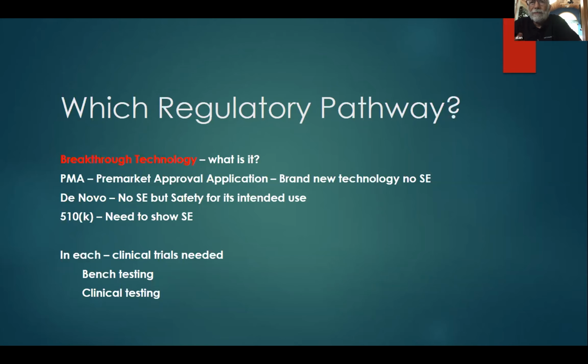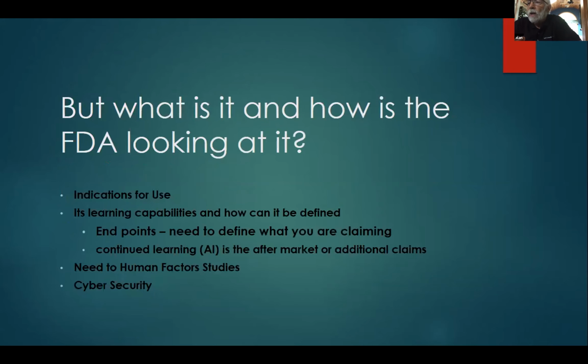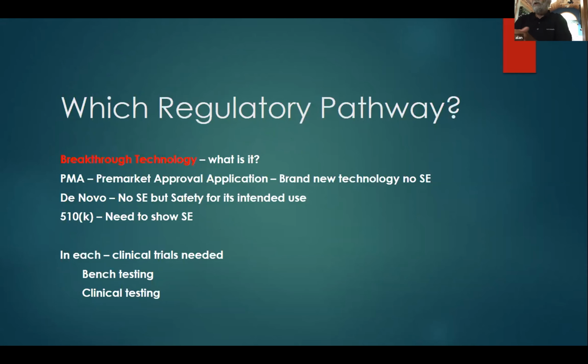The FDA was at one time thinking of reducing it down to a 510K after 4 PMAs. The FDA has decided against that, and that was in the original regulations or the original policies, but the FDA has never implemented that. You will see some devices that were PMA or Class 3 that were reclassified down into Class 2. So that does happen periodically. Now, in either case, whether you have a PMA, a de novo, or a 510K, you would need clinical trials. You would have to do bench testing, and you'd have to do clinical testing. So no matter which route you go, the FDA is expecting to see bench testing and clinical trial testing for those types of devices.